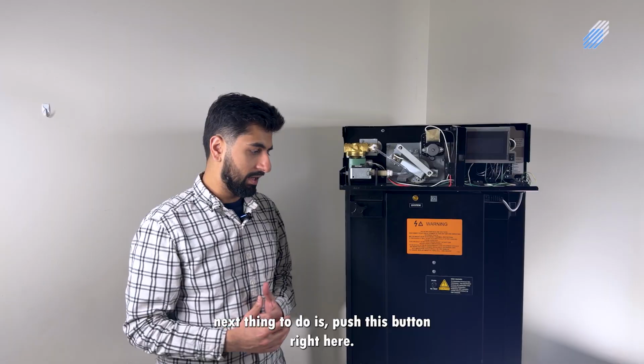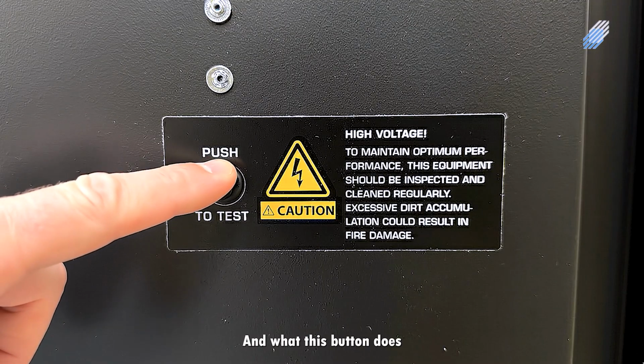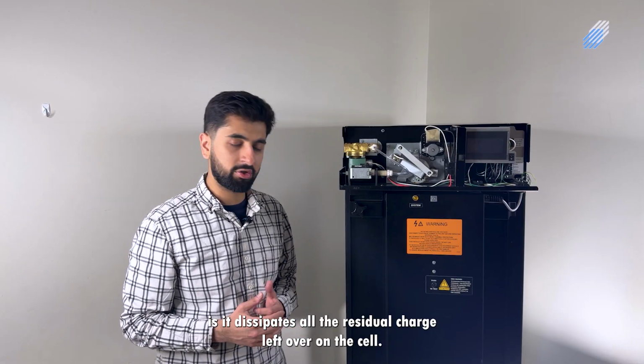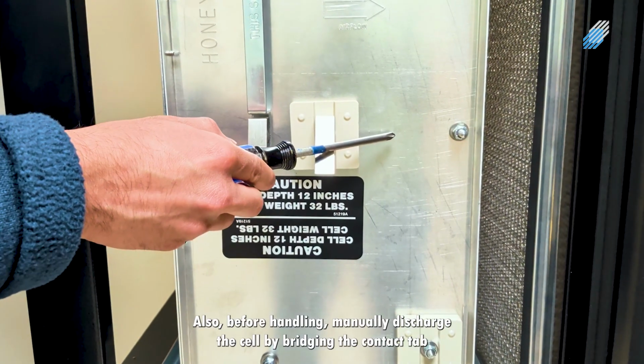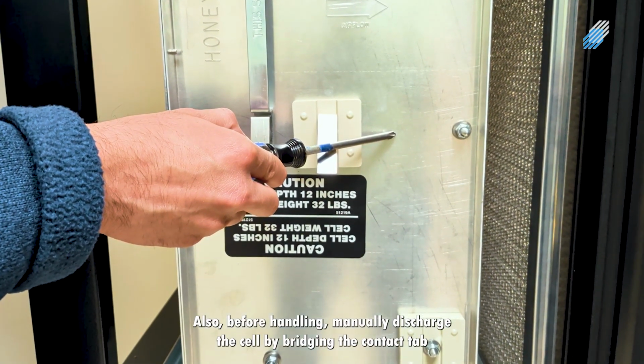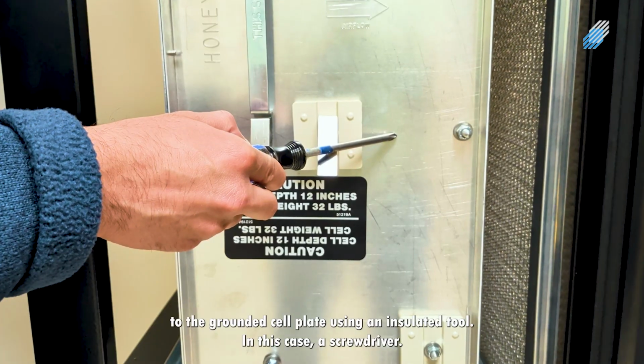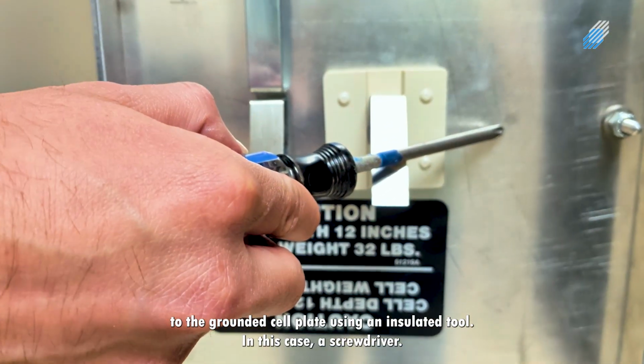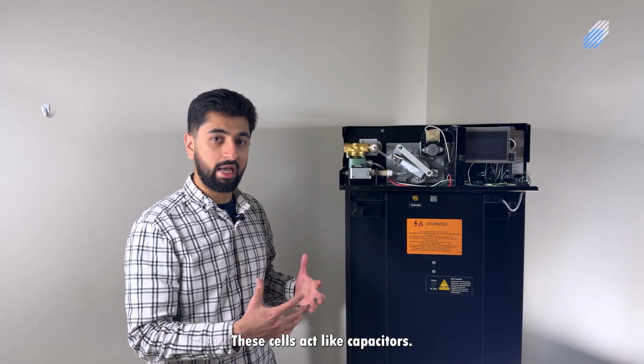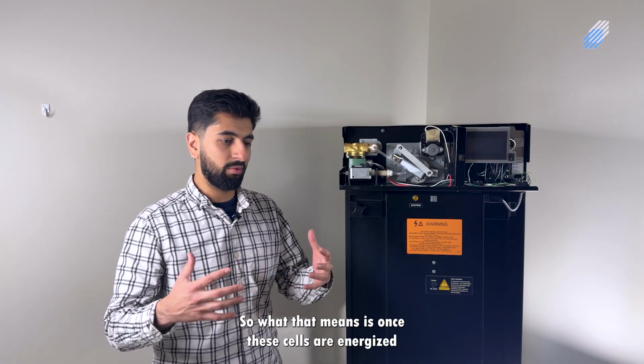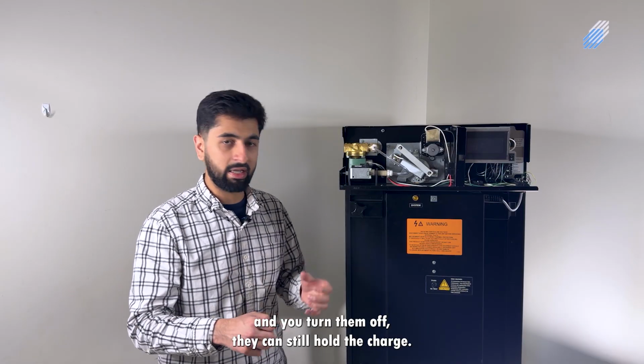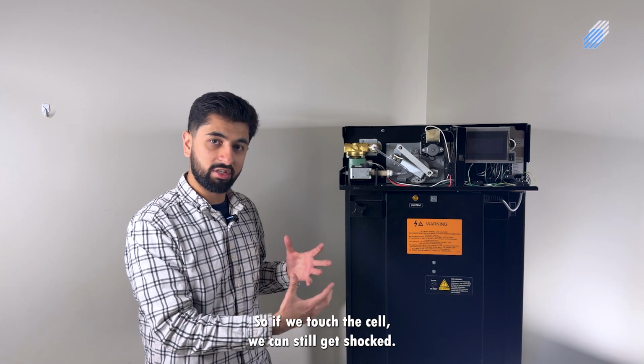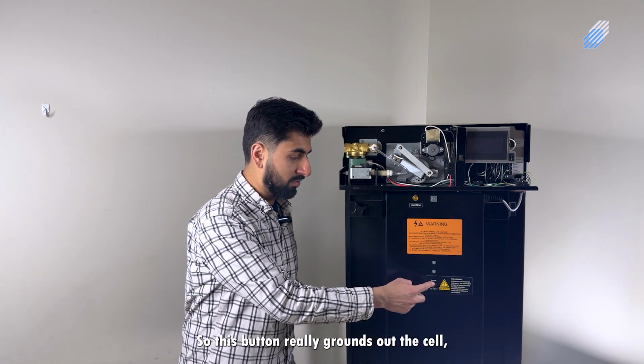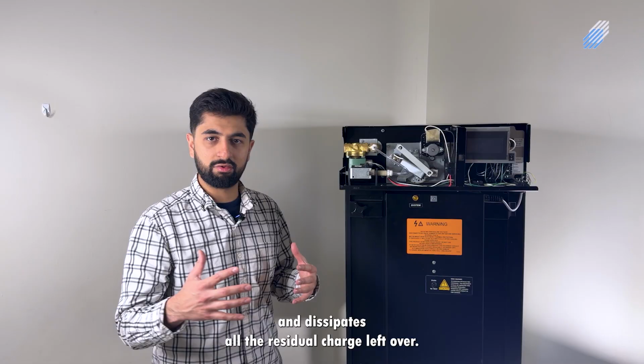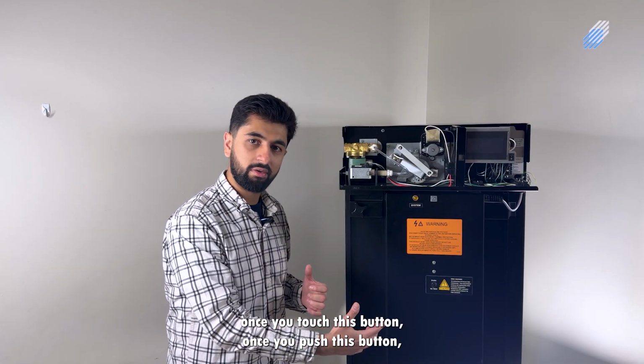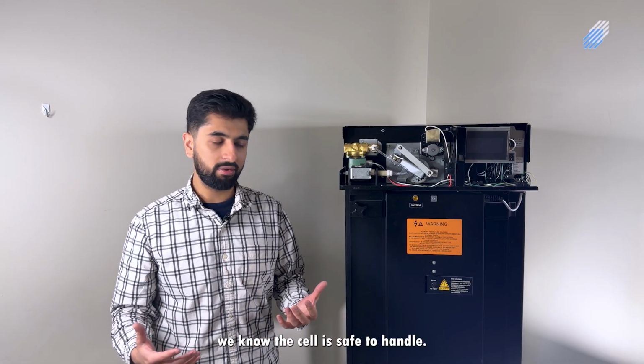Next thing to do is push this button right here. What this button does is it dissipates all the residual charge left over on the cell. Also, before handling, manually discharge the cell by bridging the contact tab to the grounded cell plate using an insulated tool, in this case a screwdriver. These cells act like capacitors. So once these cells are energized and you turn them off, they can still hold a charge. If we touch the cell, we can still get shocked. This button grounds out the cell and dissipates all the residual charge left over. Once you push this button, we know the cell is safe to handle.